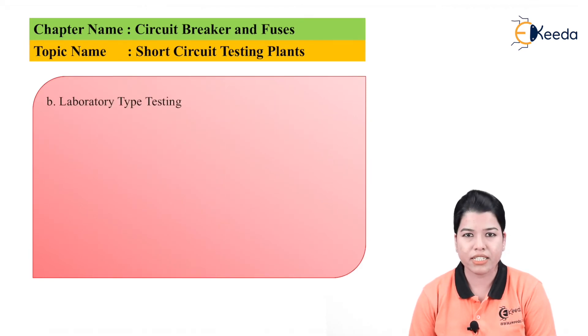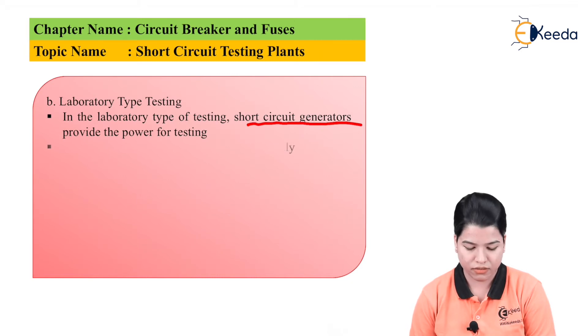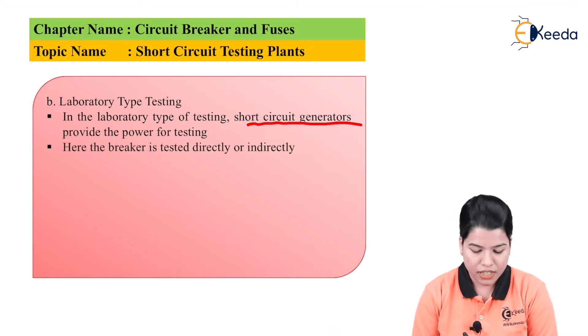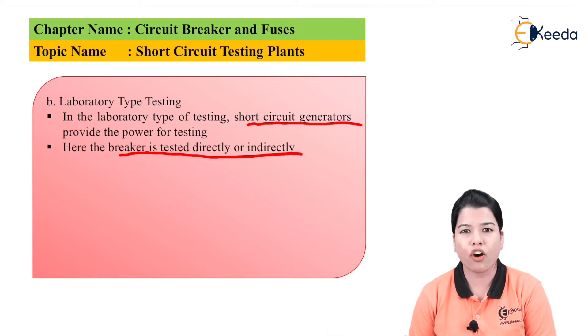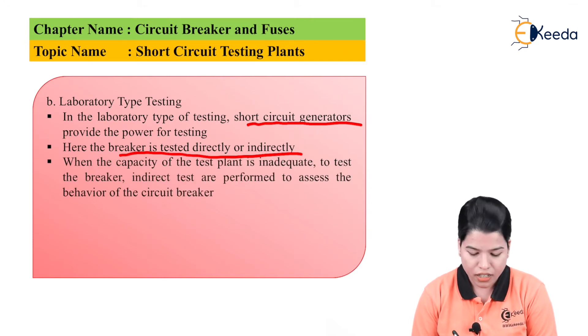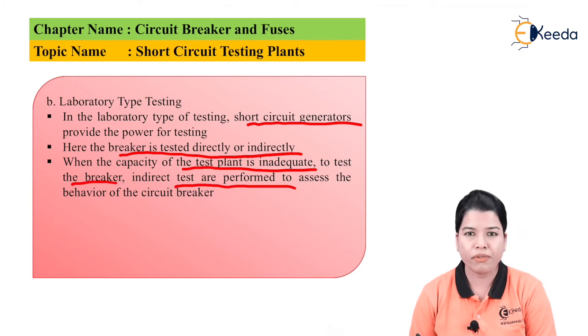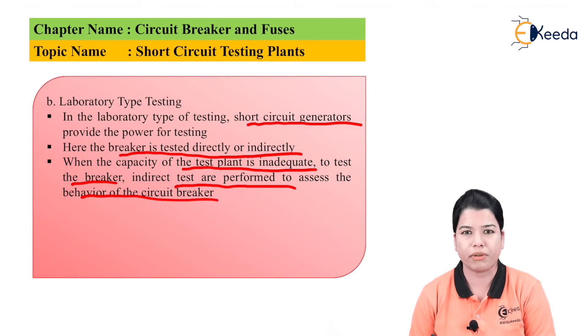In the laboratory type of testing, short circuit generators are provided for the power testing. The breaker can be tested either directly or indirectly. The short circuit generators provide the short circuit voltage for testing the circuit breaker. When the breaking capacity of the test plant is inadequate, an indirect test can be performed to assess the behavior of the circuit breaker. There are two types of tests: direct test and indirect test.